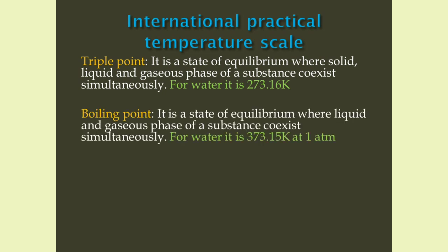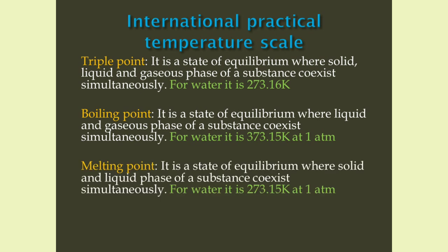International practical temperature scale. It consists of some reference temperatures like triple point, boiling point and melting point, and is formulated to calibrate temperature measuring instruments. The triple point is a state of equilibrium where solid, liquid and gaseous phases of a substance coexist simultaneously — for water, it is 273.16 Kelvin. The boiling point is a state of equilibrium where liquid and gaseous phases coexist simultaneously — for water, it is 373.15 Kelvin at 1 atm. The melting point is a state of equilibrium where solid and liquid phases coexist simultaneously — for water, it is 273.15 Kelvin at 1 atm.